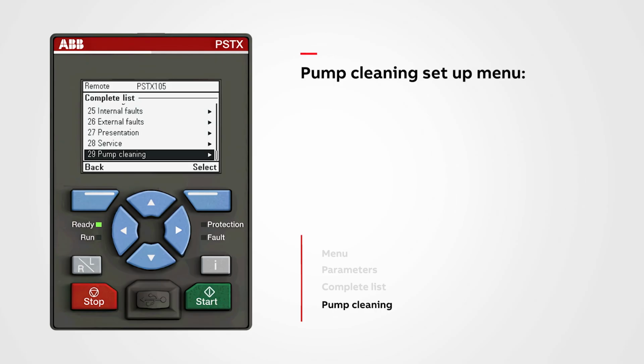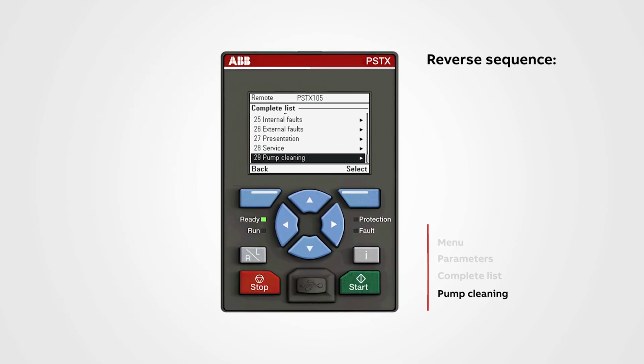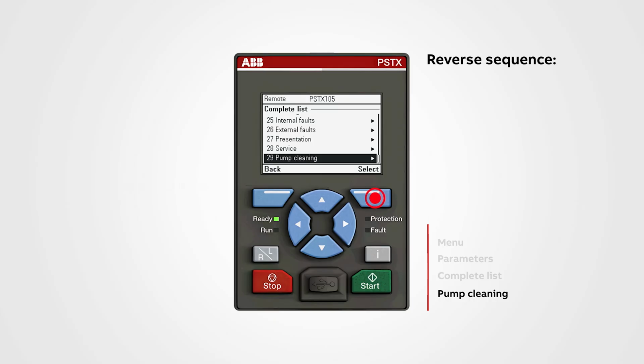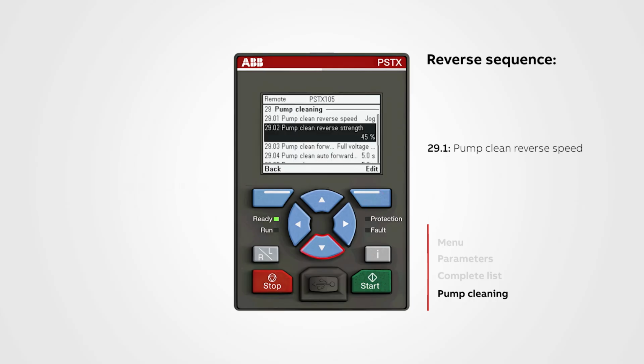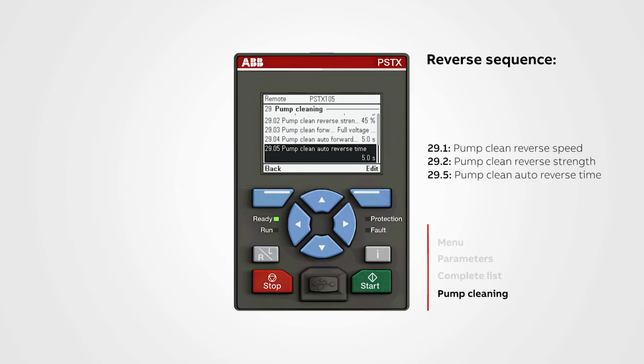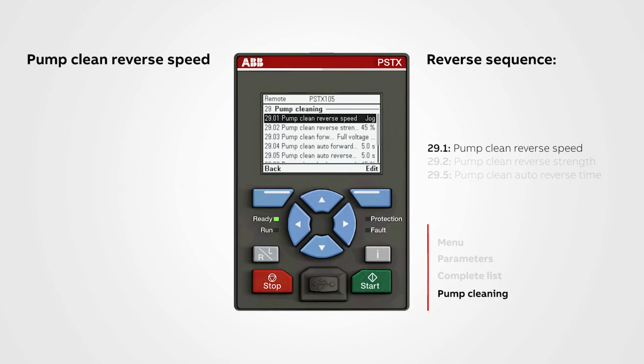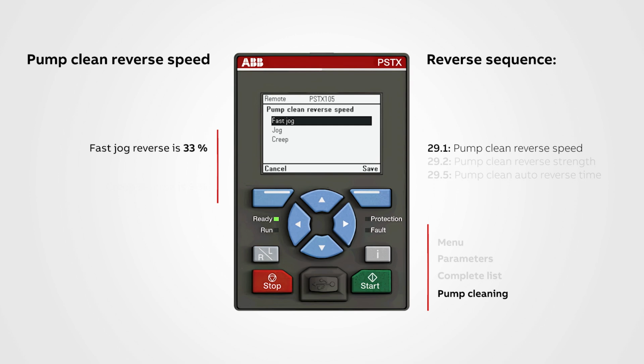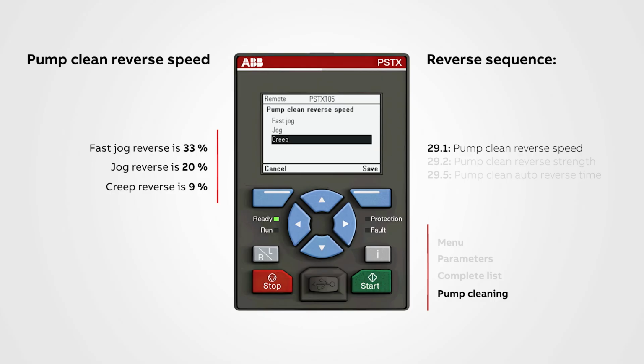So let us start with the first step in the sequence. The reverse direction, where we have 3 parameters to set: 29.1, 29.2, and 29.5. We start with the parameter 29.1, pump clean reverse speed. This sets the slow speed reverse. The fast jog reverse is 33%, the jog reverse is 20%, and the creep reverse is 9% of the nominal motor speed. The default value is jog.